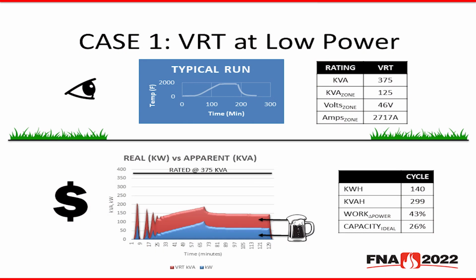This cycle consisted of a ramp up to and hold at 1800 degrees Fahrenheit. So on the surface, everything appeared fine. This run was completed without any issues. That is until we examine the electrical characteristics of the furnace. The graph below shows the total power consumption of the furnace, shown in blue and red. The red area represents kVA, which is the total power, and the blue area represents kW, which is the power that's doing work in an application.